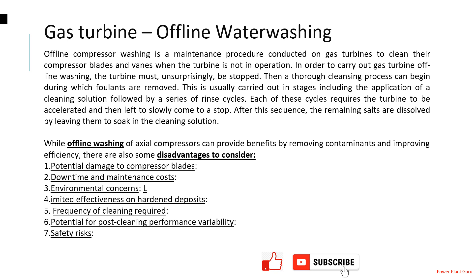This rinse cycle is repeated so that you eventually get clean water coming out. We will see how the first, second, and final stages of cleaning show increasing water clarity and the corresponding benefit. You can get two to three percent improvement in compressor efficiency with offline water wash, though it depends on conditions. If washing is done after a year of operation the benefit will differ from washing done after six months — so the numbers vary but the concept remains the same.